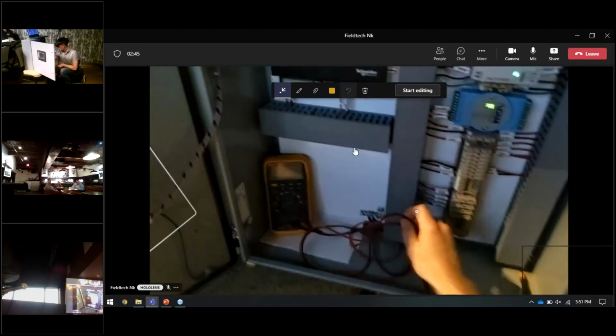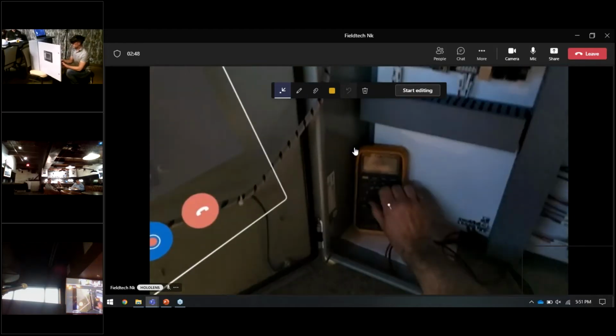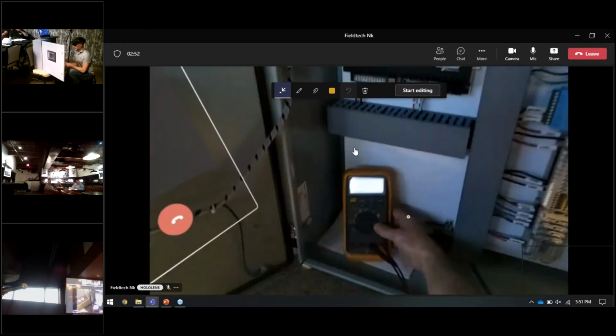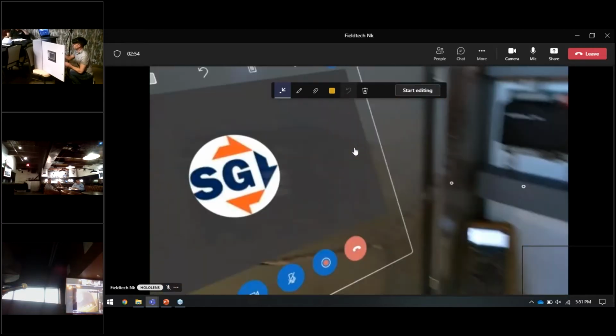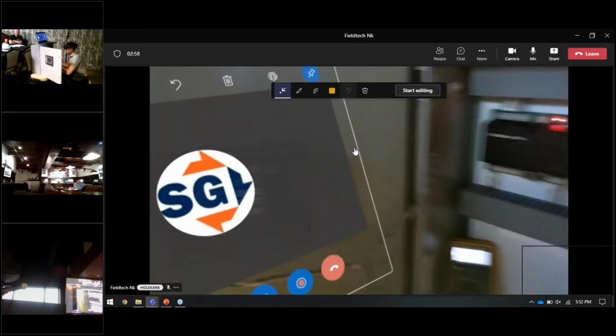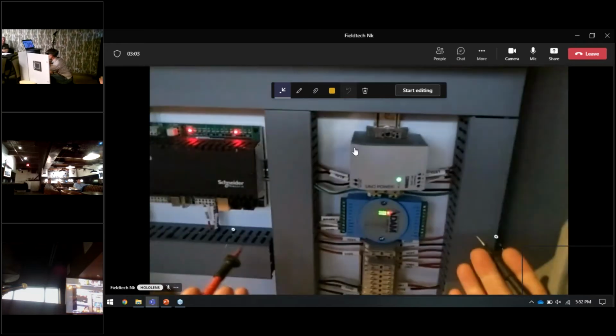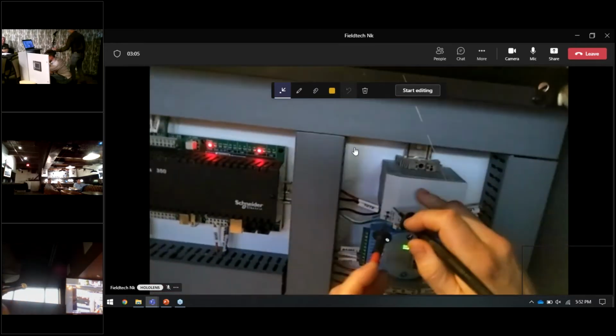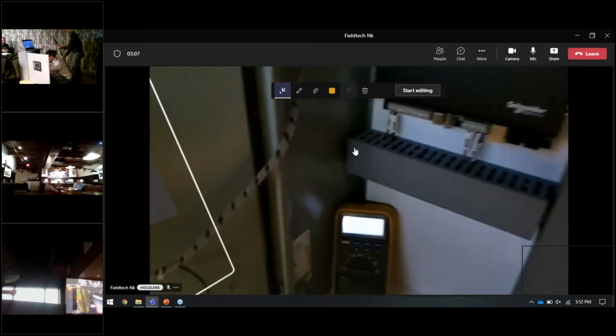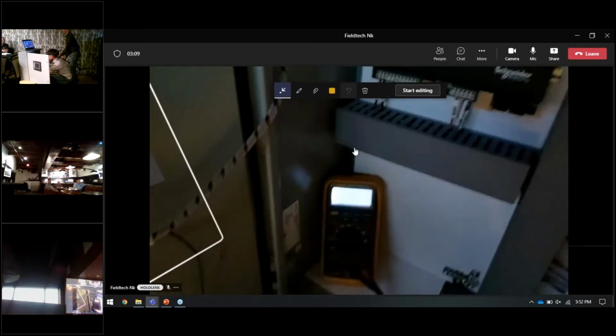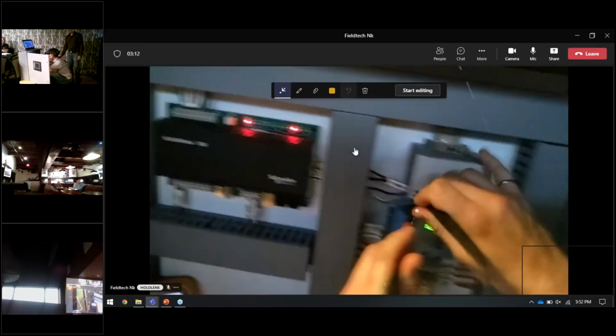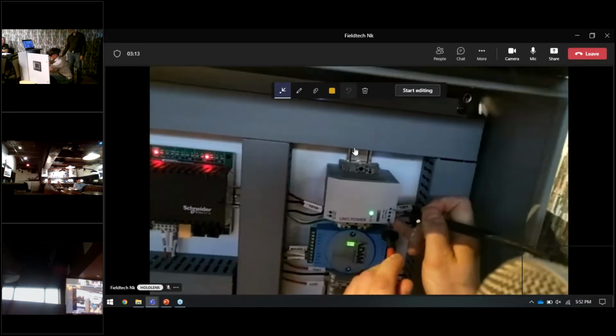I have my electrical meter in the panel already. Turn it on, make sure that you guys can all kind of read it. And if you imagine I'm talking to a person on the other end of the speaker, I can say, hey, I see the power supply on, I have good voltage between the line and the neutral, I'm reading 120 volts. But when I go to the output, it's not reading anything.